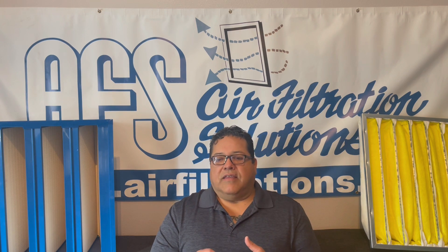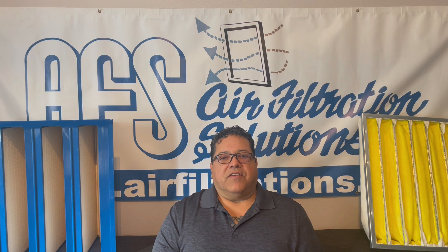It all depends on what you want as an engineering director of a hospital or healthcare facility. In my experience, I see a lot of moisture, molds, and spores in HVAC systems on air filters — happens quite often, more often than I'd like to see. That said, I'd have to give Fiberbond products the advantage when it comes to molds and spores, because with Sporax it just doesn't happen. It's protected regardless of how long you leave these filters in, and the agent even remains active after you dispose of the filter.